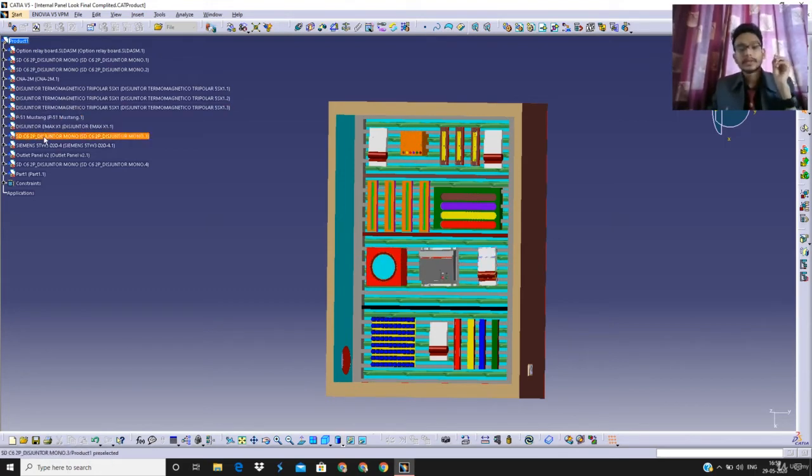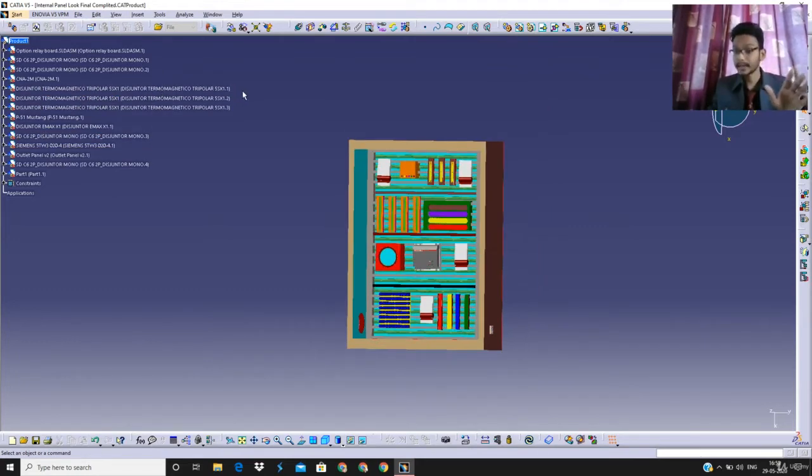All the input output switches, all the MCBs, all the contactors, all the cables must be labeled properly with the BOM, which is known as the bill of material sheet, which must be provided to every operator who is going to operate the control panel for the specific application. Now a separate external disconnection and earthing contactors should be used for a dual power supply.